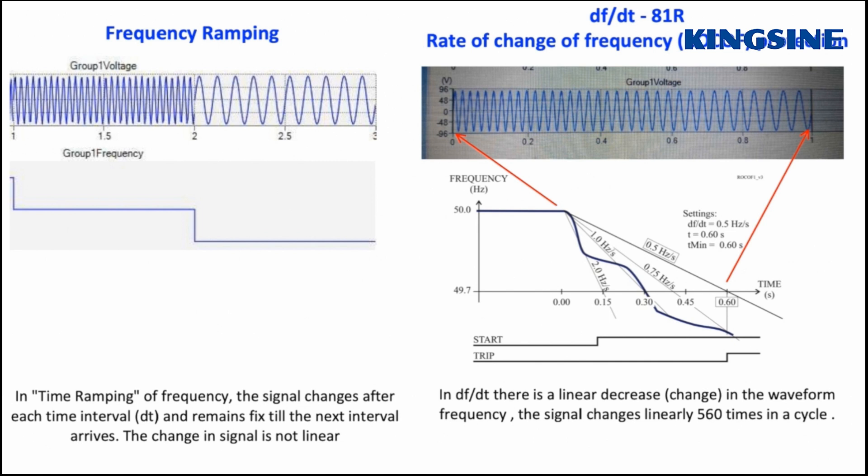As we can see, in both frequency ramping and DF by DT, the frequency of voltage signal is changing with respect to time. The only difference is that in frequency ramping, the rate of change is not linear. The signal changes after fixed time intervals and remains constant till the next interval. On the other side, in DF by DT, the signal changes linearly 560 times in a cycle.